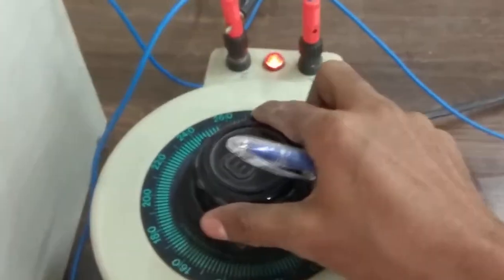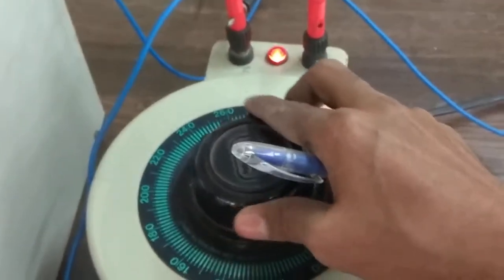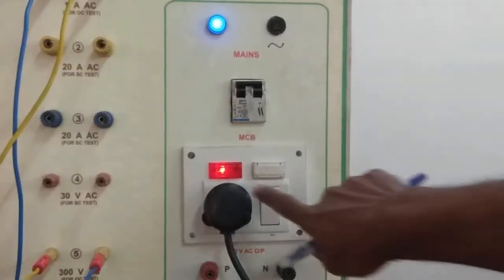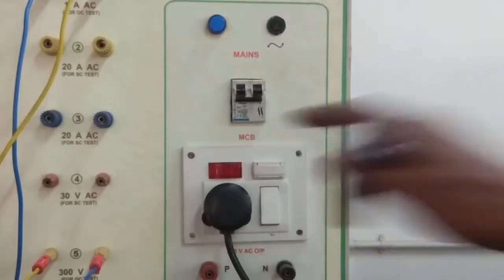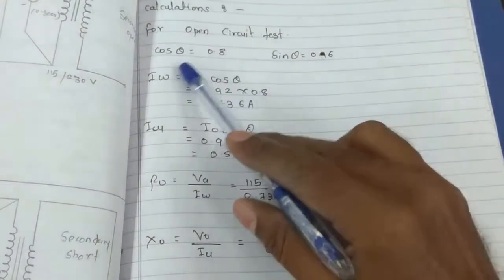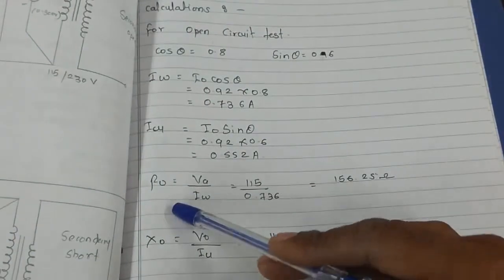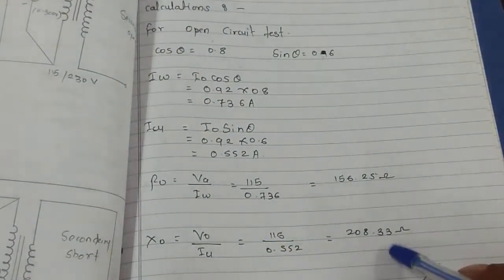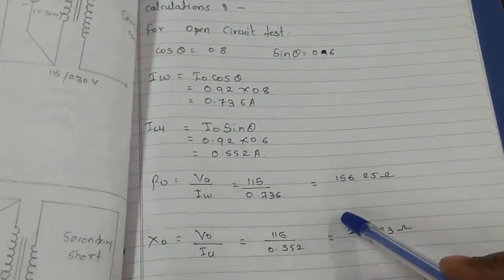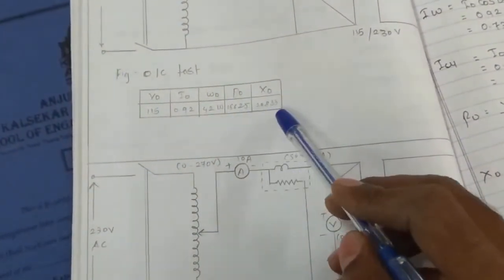Now we will bring the variac to the minimum position again and we will switch off the supply. For the open circuit test, after doing all the necessary calculation, we will find the R0 and X0, and after that we will note down this reading in the observation table. Now we will disconnect all the connections. We will remove all the connections.